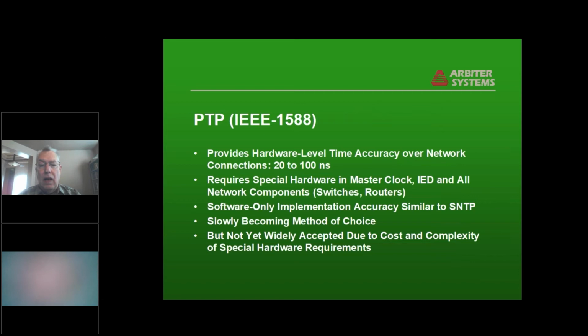More and more for high accuracy network connections, people are using PTP, which has been under development for a long time, originally, I think, 1995 or something like that. It provides hardware level time accuracy by using special hardware in all of the devices, including all the switches and routers. Everything along the path has to have hardware time tagging capabilities. What it does is recognize a certain point in the message as being a reference point and generate a hardware time tag, much like you get with a 1 PPS or IRIG signal.